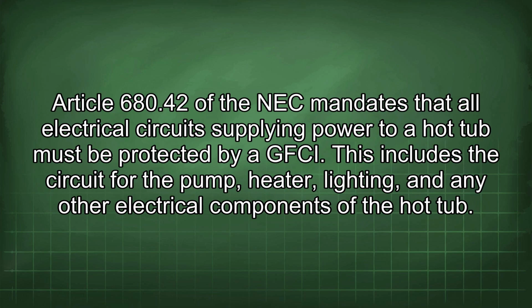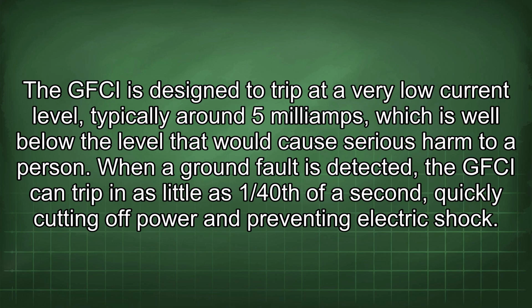Article 680.42 of the NEC mandates that all electrical circuits supplying power to a hot tub must be protected by a GFCI. This includes the circuit for the pump, heater, lighting, and any other electrical components of the hot tub. The GFCI is designed to trip at a very low current level, typically around 5 mA, which is well below the level that would cause serious harm to a person. When a ground fault is detected, the GFCI can trip in as little as 1/40th of a second, quickly cutting off power and preventing electric shock.